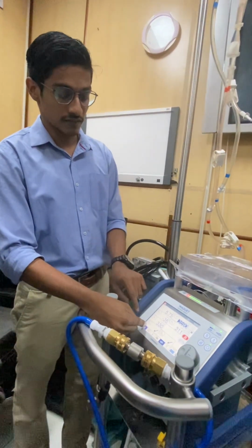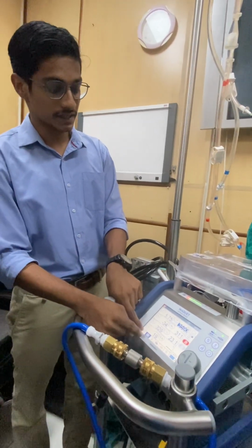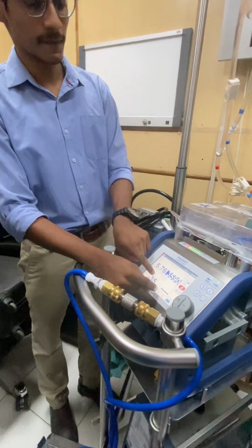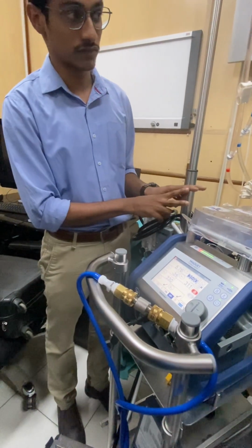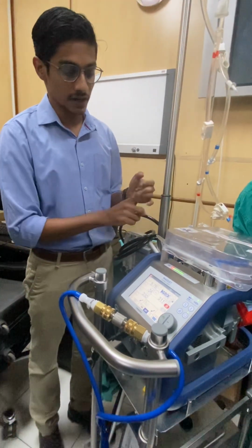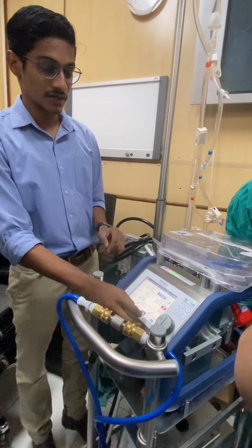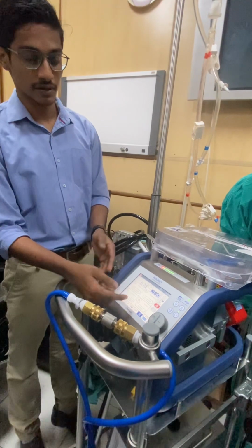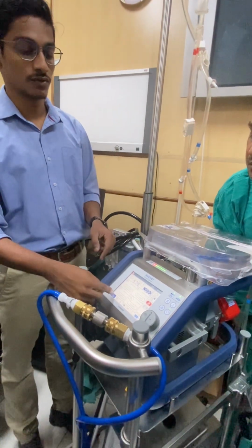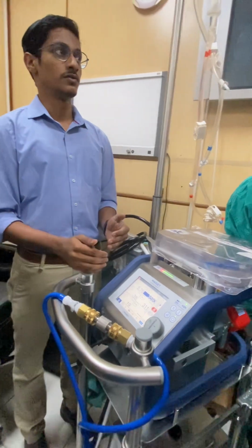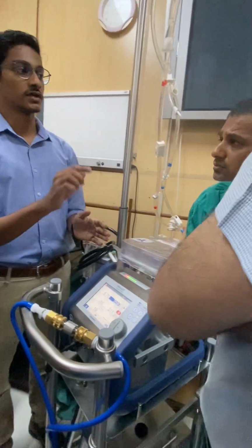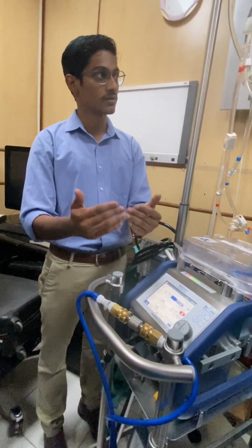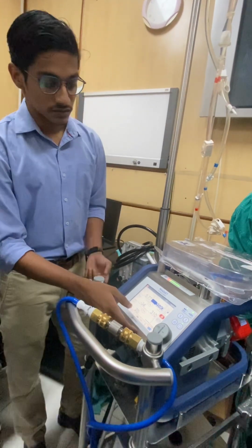So we have discussed the home button, technicals, patient parameters, transport, and intervention. For pressures we have discussed, for bubbles, and for bubble sensors we have discussed. Now we have timers. For example, when you are starting the therapy, how much time it has taken. You have multiple timers. You also have a stopwatch. For example, you are weaning down on the patient. You have reduced the support to 50%, and you can start the stopwatch and check after 1 hour, then reduce further down to 25 based upon how you want to do it.